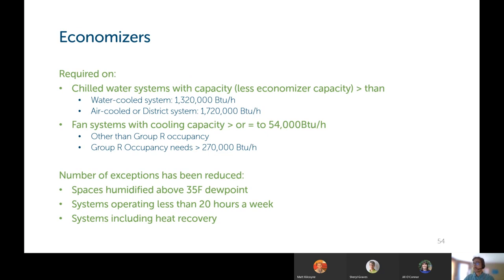So requirements for economizers, they're required on chilled water systems with capacities, after you subtract the economizer capacity, greater than 1,320,000 BTU per hour for water cooled, and 1,720,000 BTU per hour for air cooled or district systems. Fan systems with cooling capacities greater than or equal to 54,000 BTU per hour need to have economizers, other than Group R occupancies. If the building is a Group R residential occupancy, the fan system needs to be over 270,000 BTU per hour.